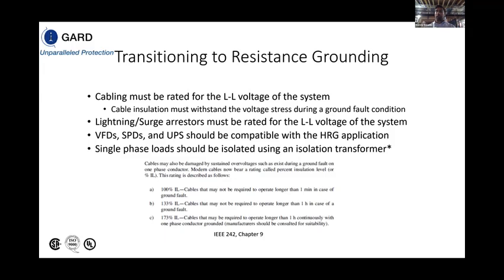In addition to that, it is highly recommended that you do not utilize single phase loads with a resistance grounded system, simply because the neutral gets elevated to the line to neutral voltage of the system. So that poses a problematic scenario for single phase loads that are relying on one of the phases as well as the neutral.